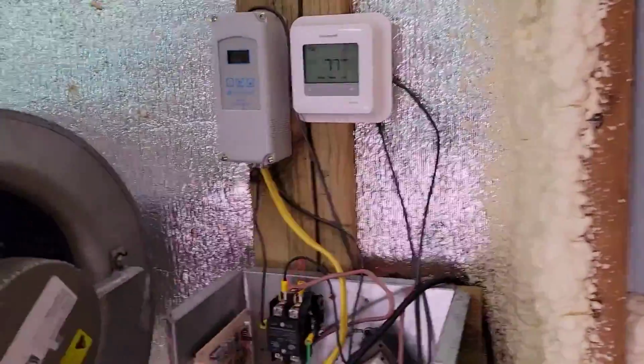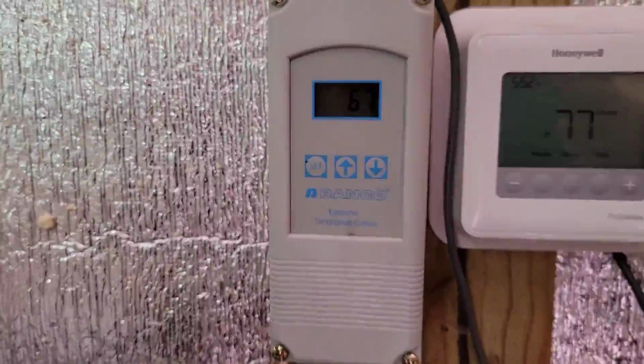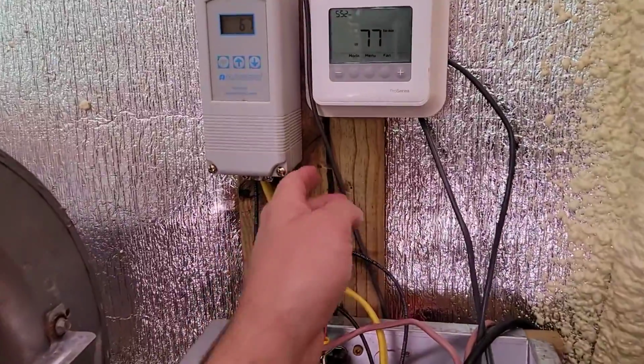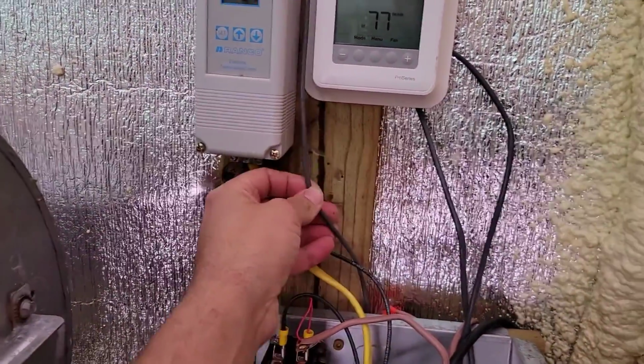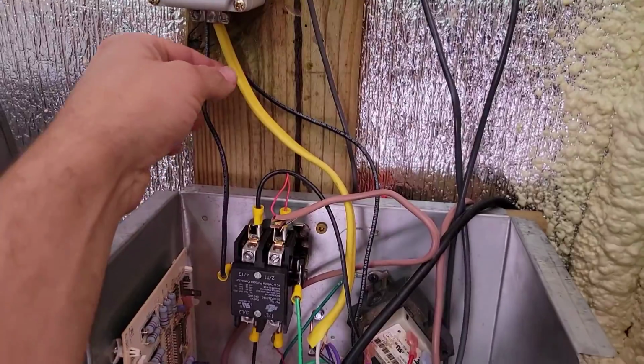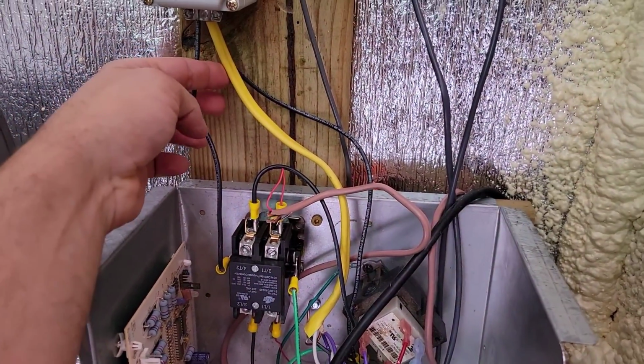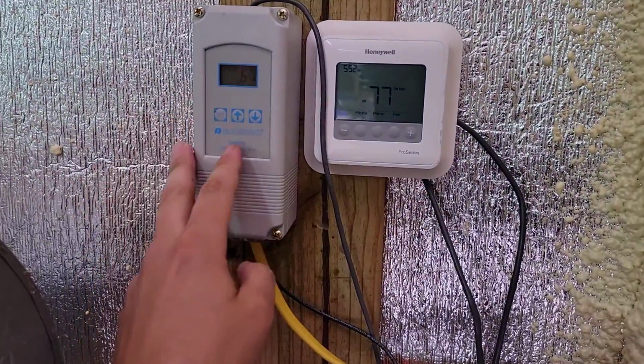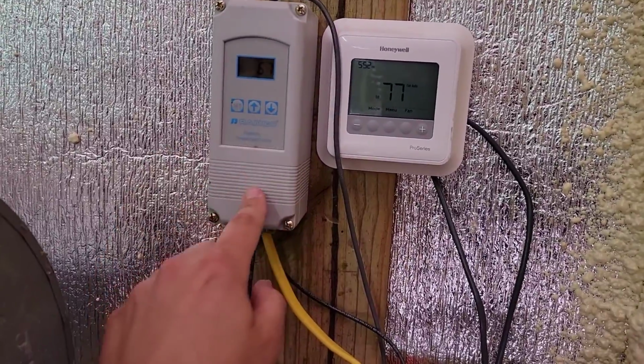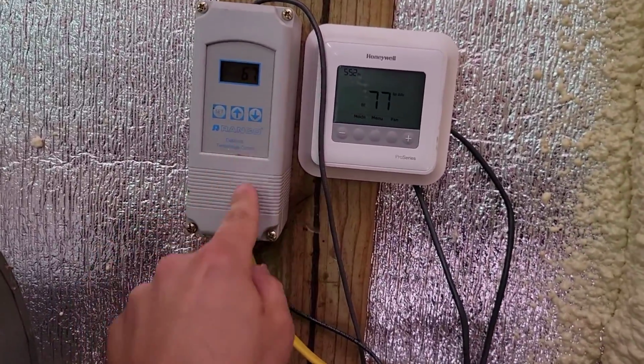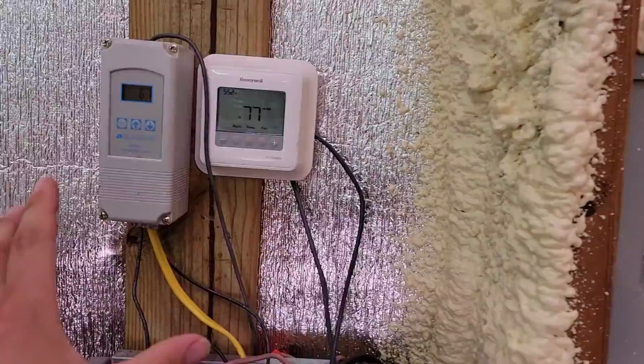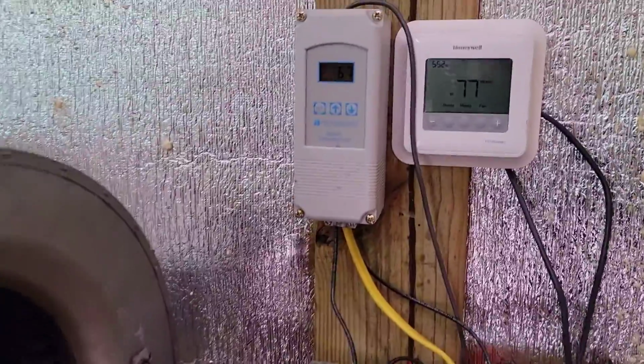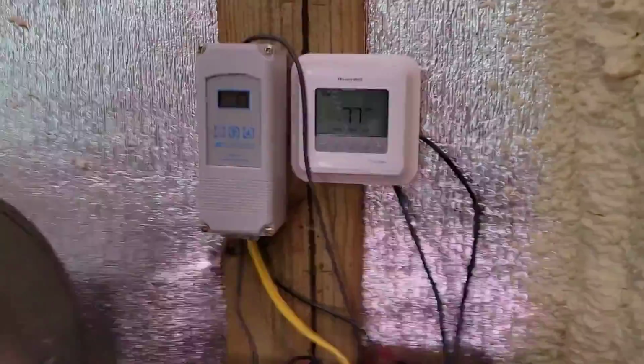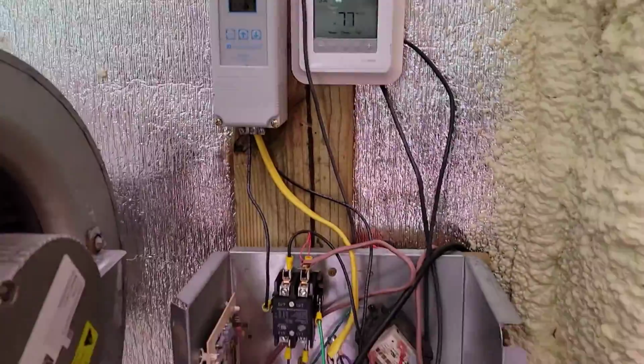All right, last thing we're going to talk about is the Ranco Stat. The Ranco Stat has a sensor that measures the water temperature, and it has a power wire that's broken that powers the Ranco controller. The Ranco controller can be 24 volts, 110 volts, or 240 volts. Make sure you check the model number, the installation instructions or wiring diagrams, and make sure if you want 24 volt, you get that.